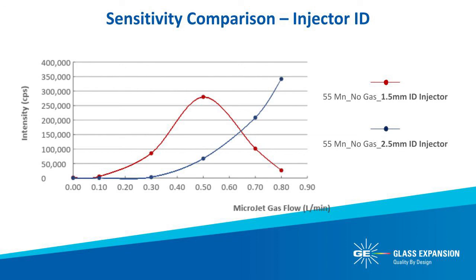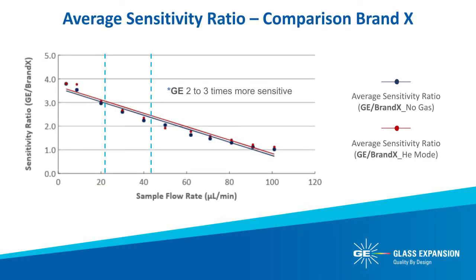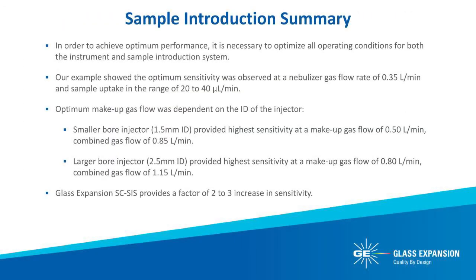This trend was similar for all 16 masses tested. We conclude our presentation with a comparison of the average sensitivity achieved with the Glass Expansion Single Cell Sample Introduction System versus another commercially available single cell sample introduction system, labeled as Brand X. The sensitivity ratio of Glass Expansion to Brand X was averaged for 16 masses ranging from low to high, at nebulizer sample flow rates from 4 to 100 microliters per minute, using a 1.5 mm ID quartz injector at 0.35 L/min nebulizer gas flow and 0.5 L/min makeup gas flow. It is necessary to optimize all operating conditions for both the instrument and sample introduction system to achieve optimum performance, and these optimum conditions should be used as guidelines and a great starting point for your own optimization.